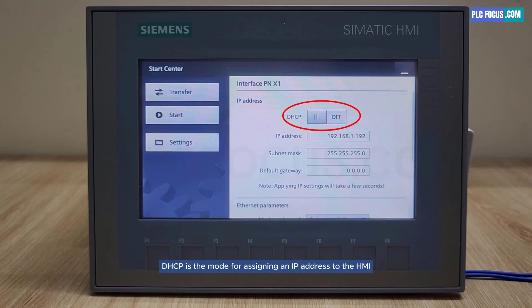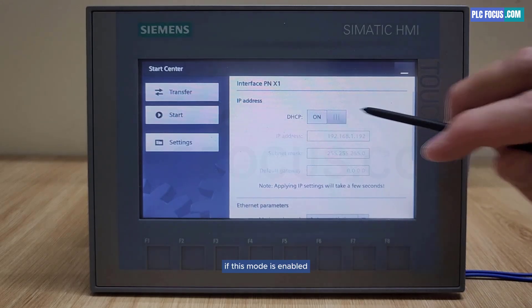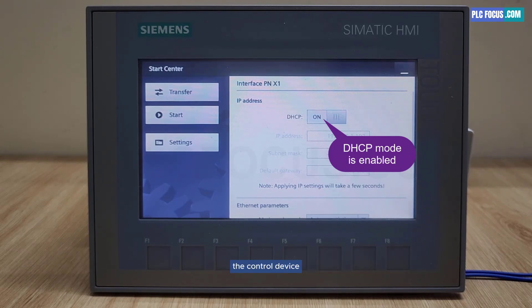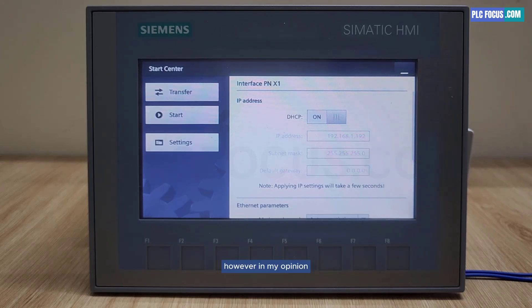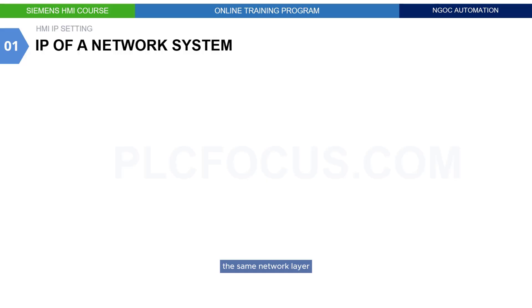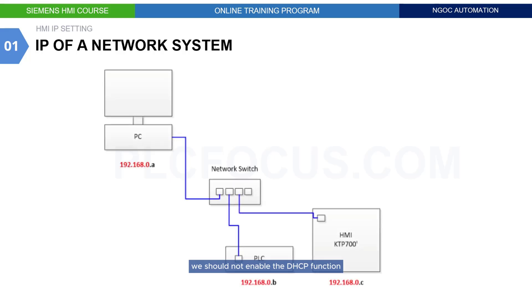DHCP is the mode for assigning an IP address to the HMI. If this mode is enabled, the HMI will automatically obtain an IP address within the same network layer as the control device. However, in my opinion, to ensure that control devices are within the same network layer, we should not enable the DHCP function.